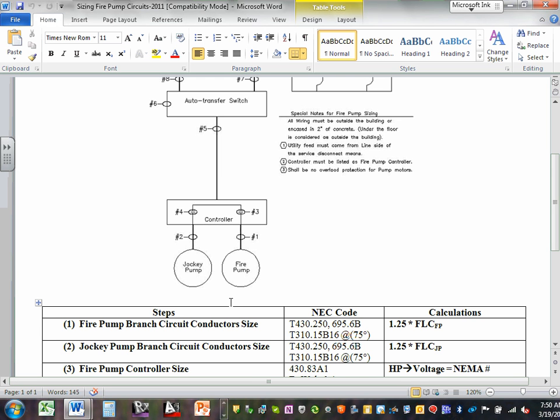Okay, so that's what we have. So let's start at the bottom. You have a jockey pump. Typically they have a jockey pump and a fire pump. You need a branch circuit. I'm sizing them. Can you see these numbers are related to the bottom table that you have? So I have 1 and 2. These are the branch circuit for the fire pump and the branch circuit for the jockey pump. Then we have a controller, 3 and 4. Can you see that?